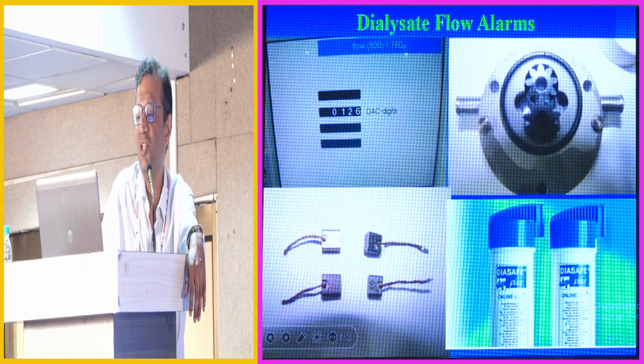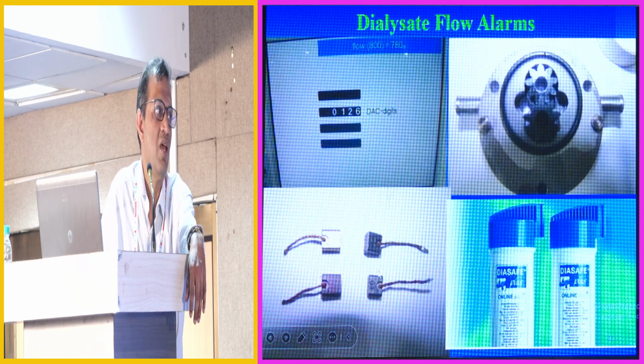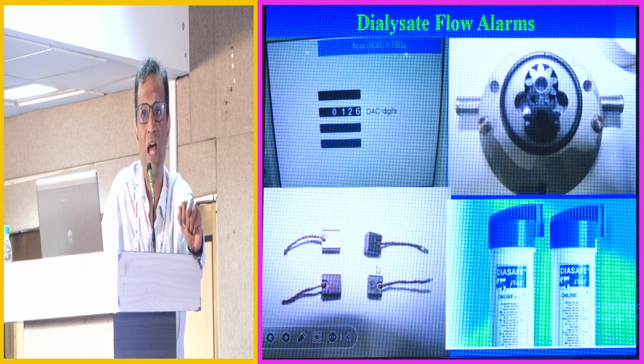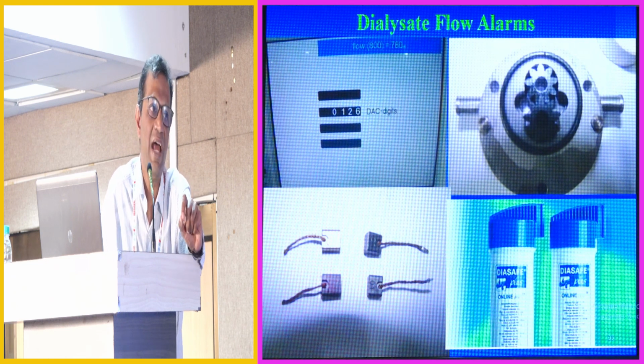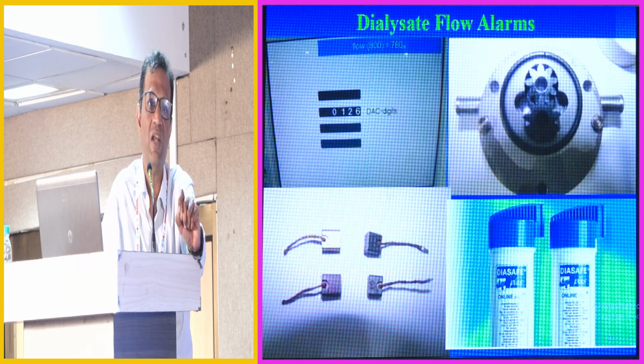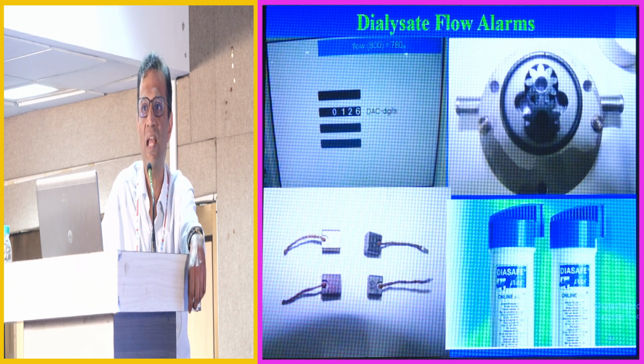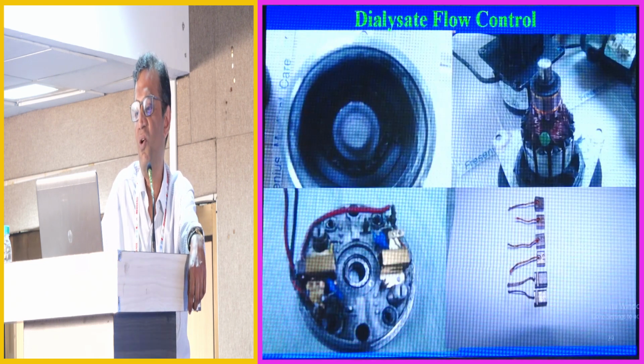So this is a new brush, and this is a brush which has been in use for some time. Over a period of time, the brush's length will fall to an extent where it no longer makes contact with the rotor, and at that point a flow alarm will occur and the brushes will need to be changed. Otherwise, no matter what adjustments are made in the calibration menu, you will not get rid of the flow alarm. So this is what the inside of it looks like.